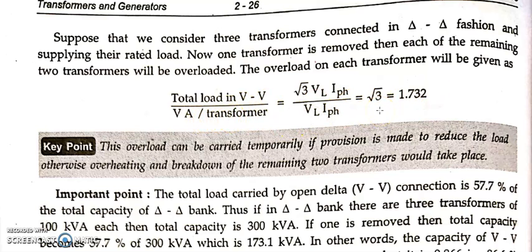That is around 1.7 times, which we can call 173%. Yes or not? 173.2% of voltage ampere, that is, the VA rating of the transformer, will be increased. Increase in the sense that much burden will be put on each of the transformers if one of the transformers fails in the bank of 3 single phase transformers. Okay.